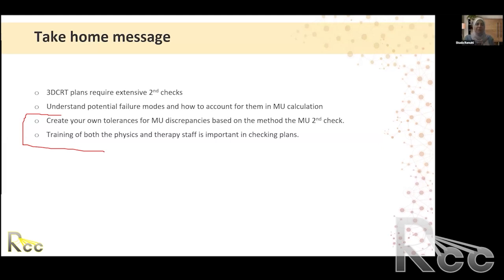The 1 centigray per monitor unit sometimes could be 0.99. In some centers in the US, especially if they are part of clinical trials, they are requested to report the dose not in water, but in tissue. And the mass energy absorption coefficient ratio between tissue and water is 0.99. Now we say, water equals tissue, etc. This is good enough, right? And if you say, I'm going to calibrate 1 centigray per monitor unit, this is what the majority of people do. But if you see centers calibrating 0.99 centigray per monitor unit, it means that they are participating in a clinical trial that requires them to report dose to tissue instead of dose to water. So 1 centigray is good. Use that. With 0.99, you'll be reporting dose to tissue instead of dose to water.